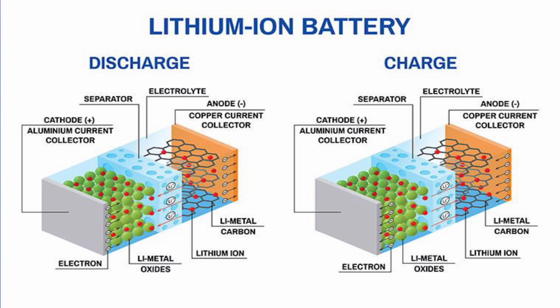UPS, an uninterrupted power supply system, is a device that provides power backup for a certain time period in case of power cut or failure. Such devices typically make use of a combination of lithium ion batteries. This is because the use of lithium ion batteries in UPS devices reduces the floor space by 50 to 80%, and a lithium ion battery based UPS system weighs 60 to 80% less than the generic lead acid based UPS device.